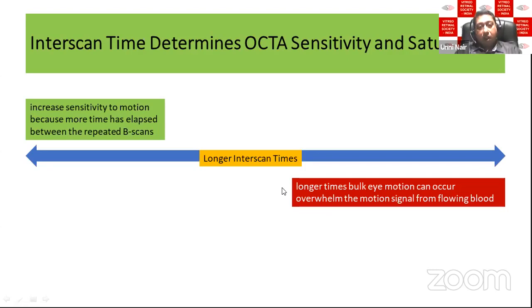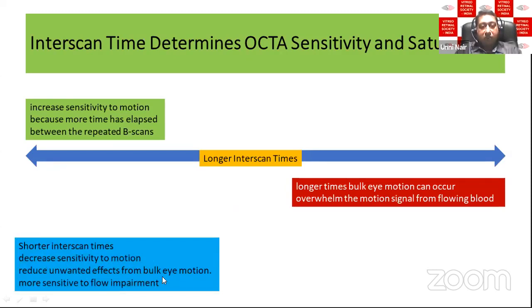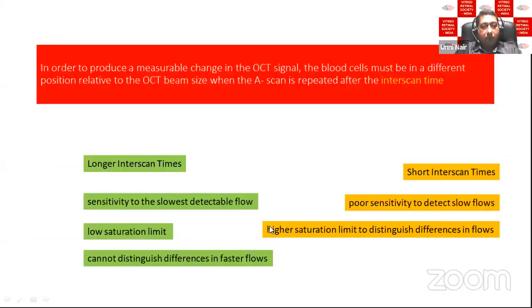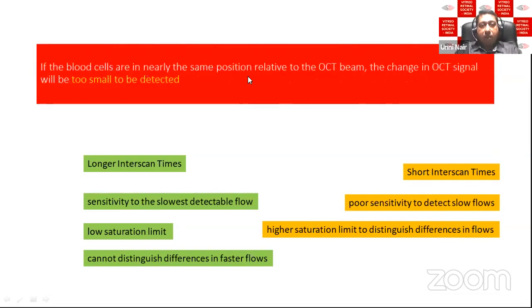A shorter inter-scan time has decreased sensitivity but fewer bulk eye motion artifacts. Newer concepts like VISTA — variable inter-scan time — allow varying the inter-scan time between fast or longer scans. The blood cells should have moved sufficiently to be detected; if the blood has barely moved within a very short inter-scan time the movement won't be detected. There are two concepts: sensitivity increases with longer time, but faster flows may go undetected at longer inter-scan times.